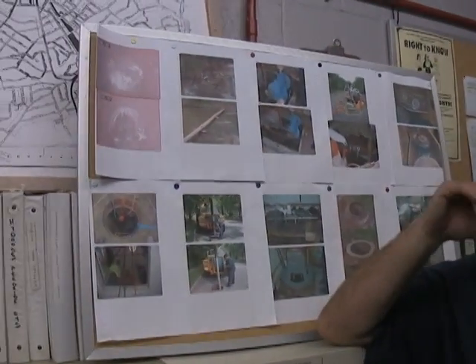This has since been lined, the whole section, because we had roots in multiple places, and this is actually a weird setup because it goes from the road into the woods and then goes down along the woods and comes back out. So this was kind of a maintenance headache. By lining it, I'm sure that we took care of some infiltration in this area, but we eliminated having to go there on a biyearly basis and clean that system.